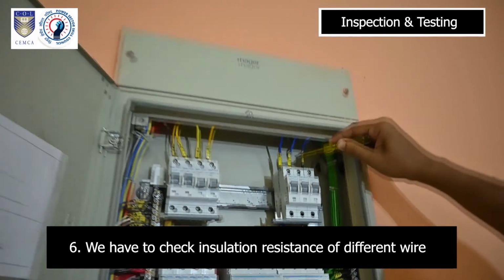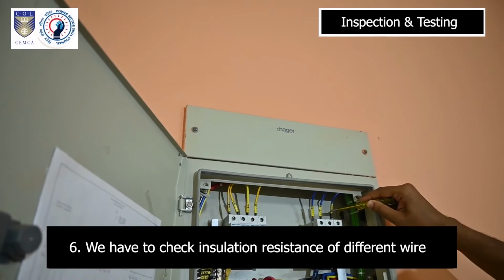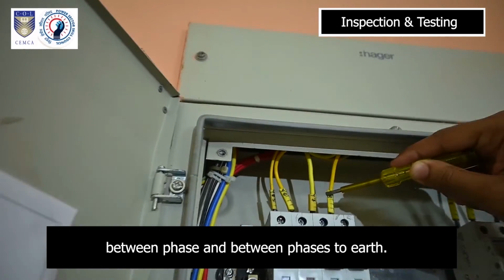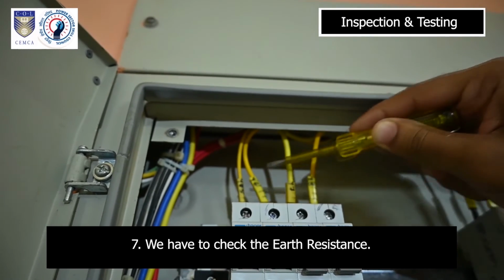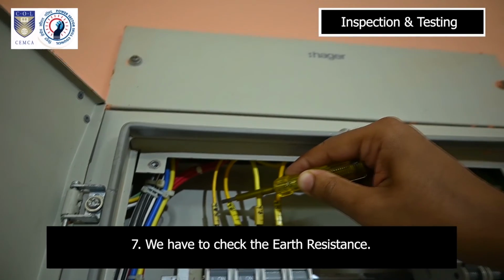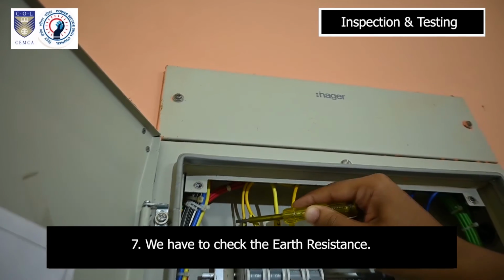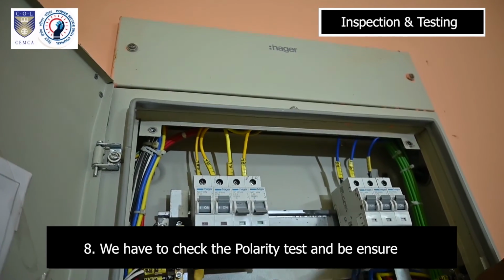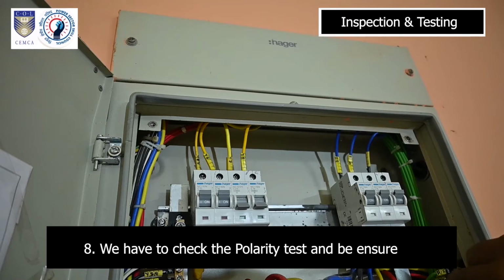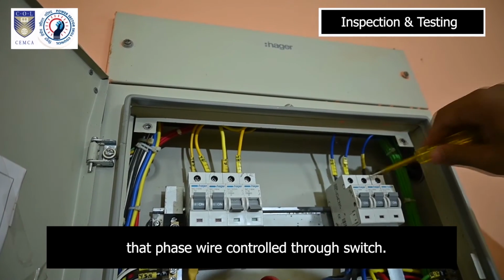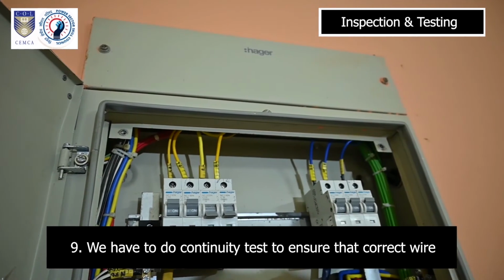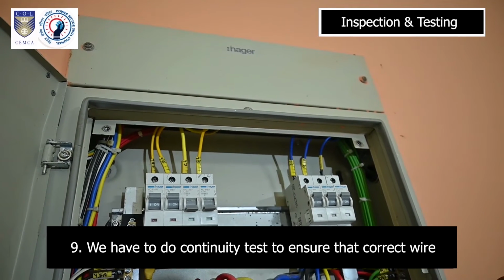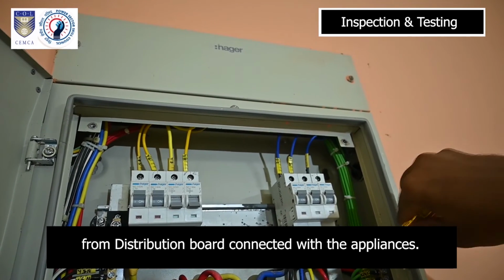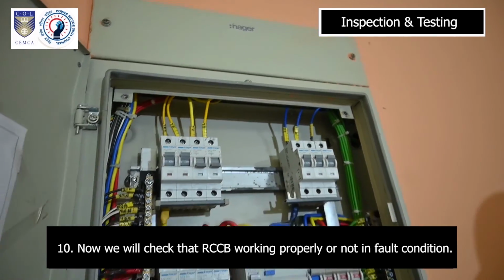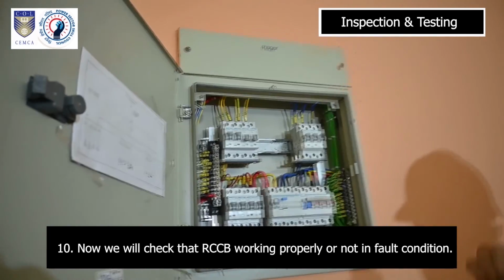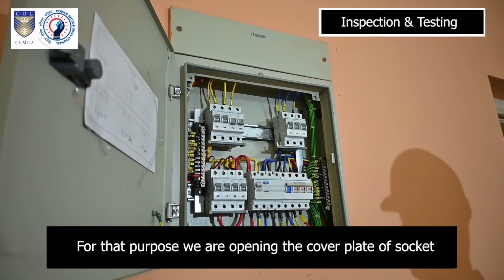6. We have to check the insulation resistance of different wires between phases and between phases and earth. 7. We have to check the earth resistance. 8. We have to do the polarity test and ensure that the phase wire is controlled through the switch. 9. We have to do a continuity test to ensure that the correct wire from the distribution board is connected with the appliances. 10. Now we will check whether the RCCB works properly in a fault condition.